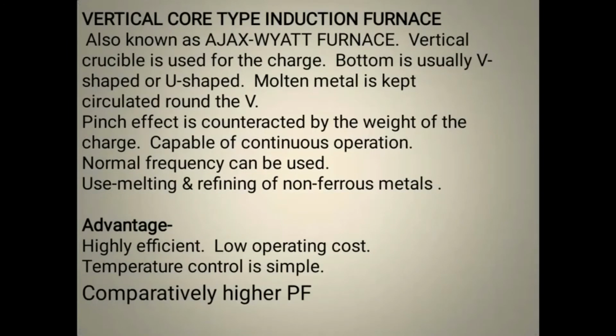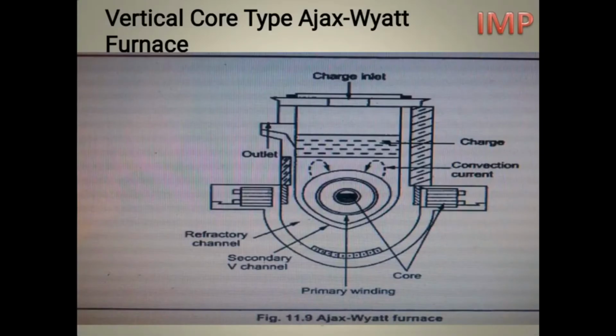The pinch effect is counteracted by the weight of the charge. It is capable of continuous operation, and normal frequency can be used, as we do not use in direct core type. It is used for melting and refining of non-ferrous metals. Advantages: highly efficient, low operating cost, temperature control is simple, and comparatively higher power factor than direct core type. This is the figure of the vertical core type Ajax Wyatt furnace, a most important question for the final exam.